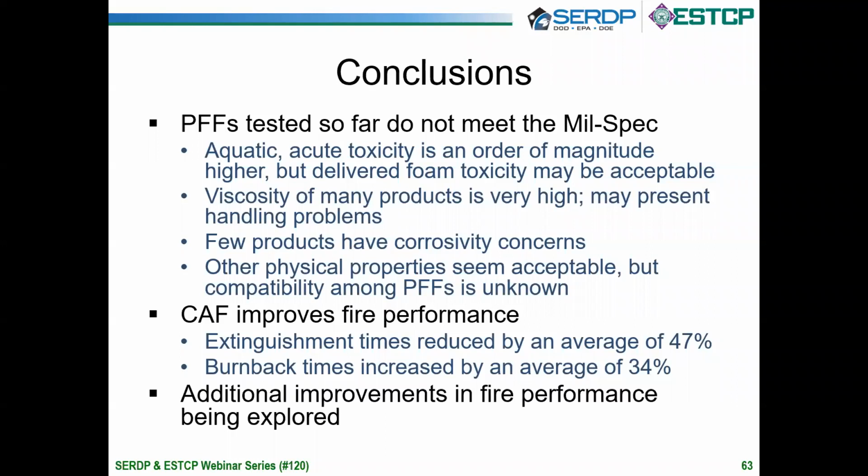The viscosity is a concern, and we're beginning to see some lower viscosity products come out. A few products have corrosivity concerns, but some corrosion inhibitors could take care of that. Other physical properties seem acceptable, but one other requirement that we have is that different products that are certified be compatible with each other. So when you switch from one product to another, you don't have to throw away the old ones. That is an unknown.